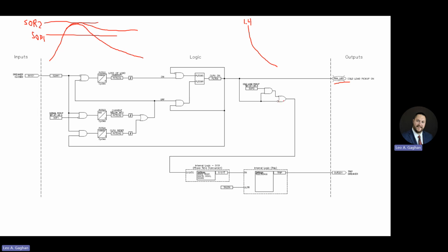Well, if cold load pickup is on, we come through here, that 1 becomes a 0. We don't pass through that part of the OR gate. Now we have to be up above our 1.9 to get through this OR gate and allow the torque equation to work. So we'll essentially snip off part of the curve there at 1.9 amps. The curve will remain unchanged, but only the portions to the right of this line will be allowed to operate. And then, of course, as the overcurrent element operates, it'll hit the trip equation, it'll trip the breaker, and such.